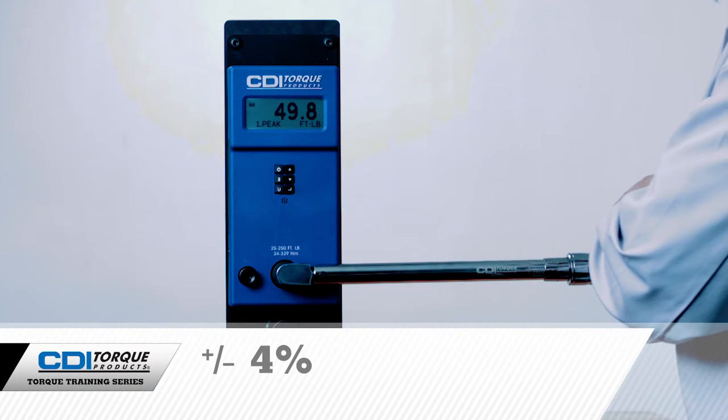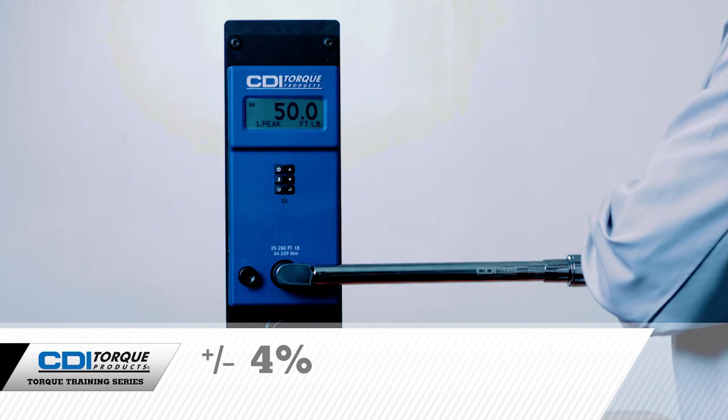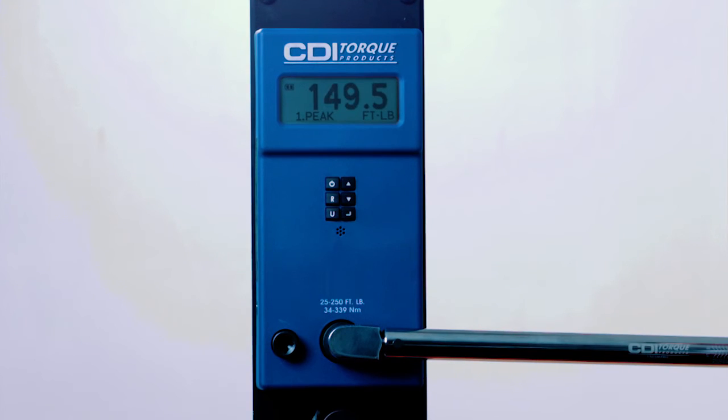The reading on the tester should be within plus or minus 4% of the setting on the torque wrench. If the reading on the DTC is greater than or equal to plus or minus 4% of the setting on the wrench, then the torque wrench is out of tolerance.